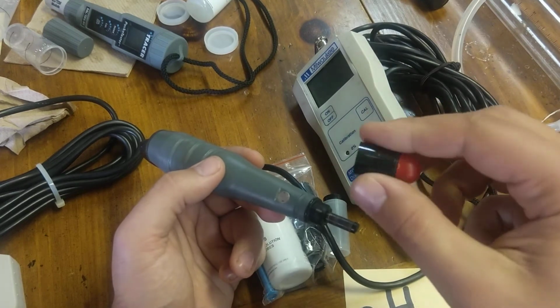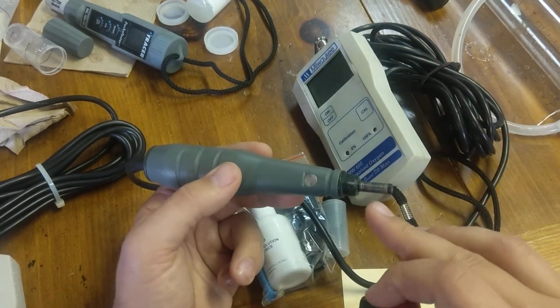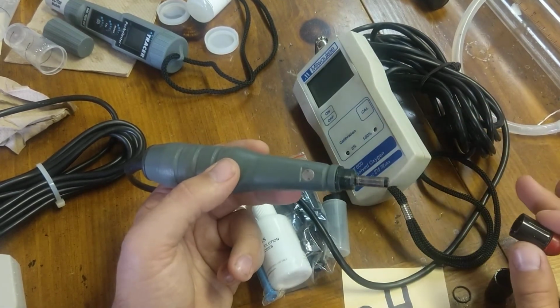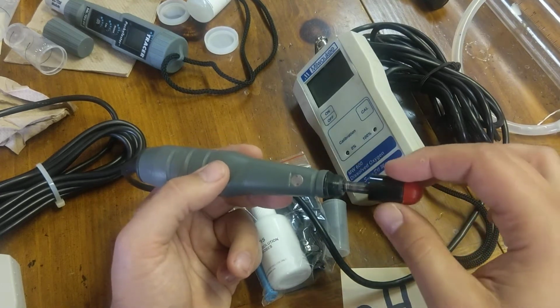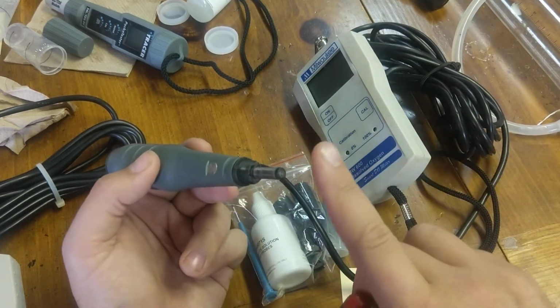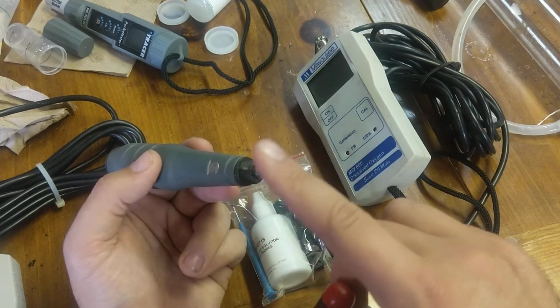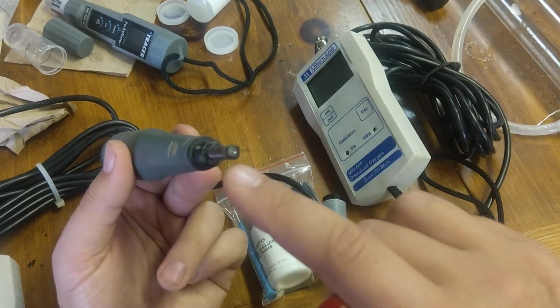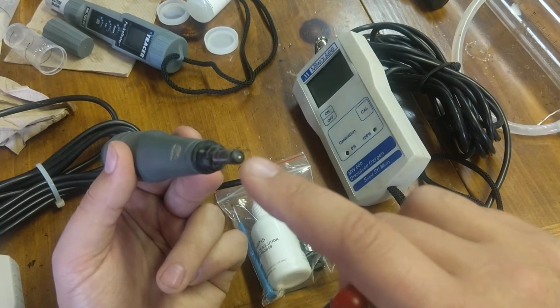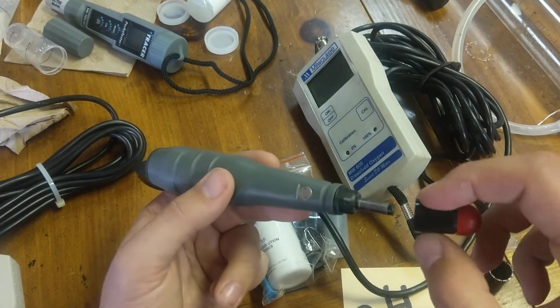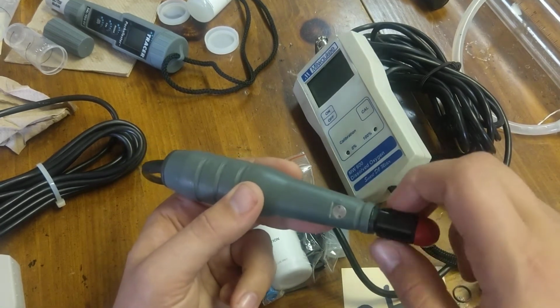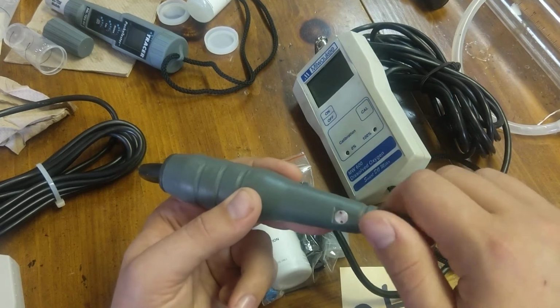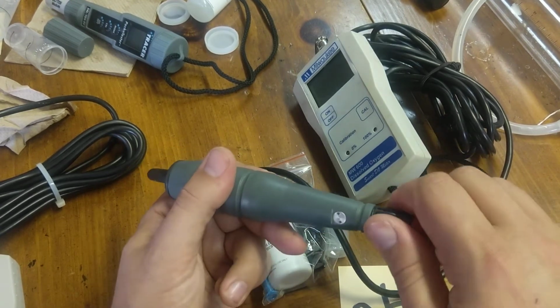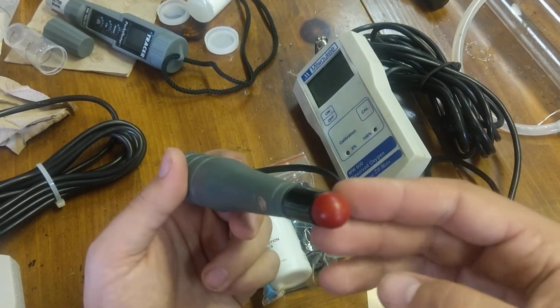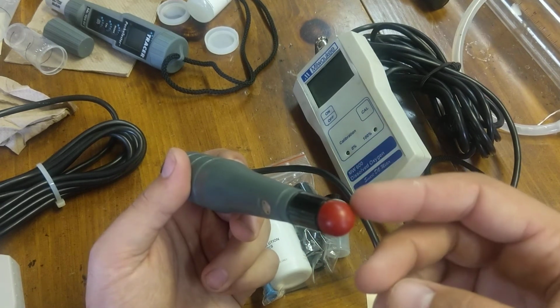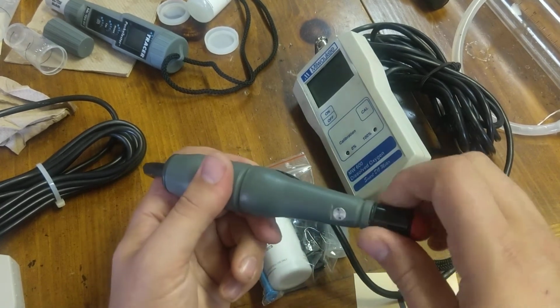I usually use this cap for that. In this case, you want to make sure it's completely dry. I would set it out overnight. Again, do not touch any of this part here, especially the platinum end on here. That is extremely sensitive. You do not want to touch that because it will scratch it and end up reducing the accuracy or damaging the probe. So this right here kind of protects the end.